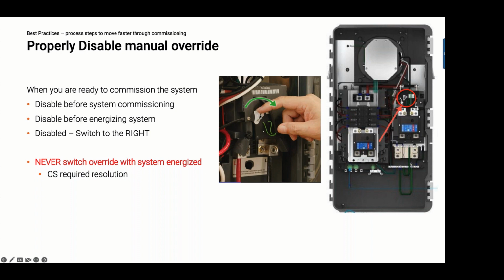You want to do this before you commission the system, before you energize the system, actually. So when your system is installed and all of the components are installed, so all the battery components, the microinverters, before you energize the system, you remove this out of override position. And that's the only time you want to do this. If you don't have your batteries installed yet and you just have the system controller, don't take it out of the override. It's when you're ready to commission the system, everything is installed, go ahead and remove it out of the override by flipping the switch from the left to right.